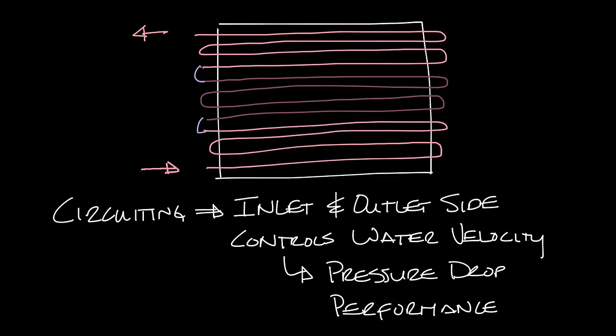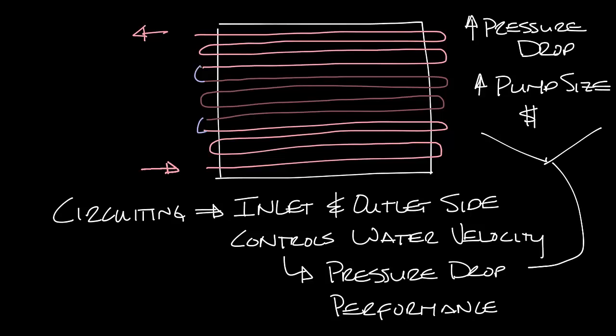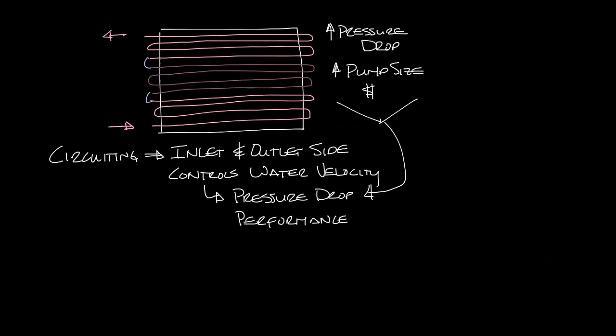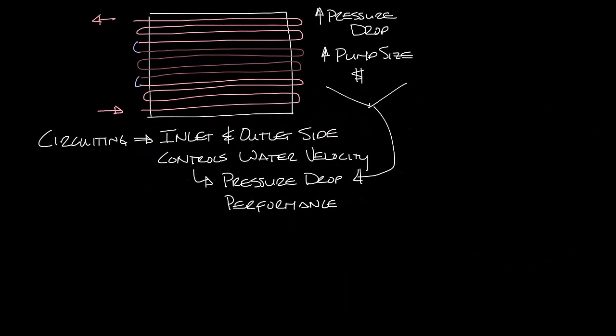Running one long tube like this would increase your pressure drop across the coil which will affect the size of your pumps and can increase costs. So those are related to pressure drop. Let me make a little bit of room here so I can talk about performance.